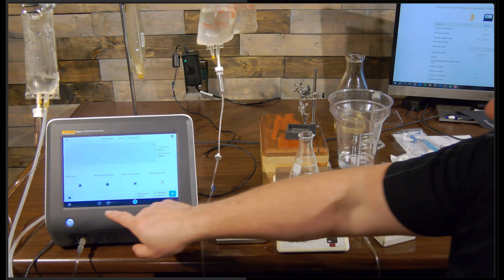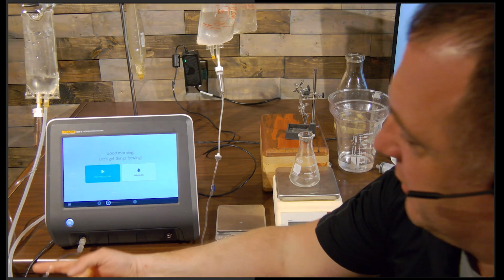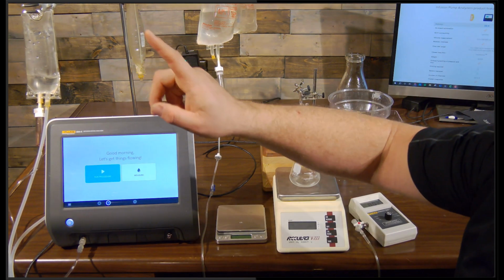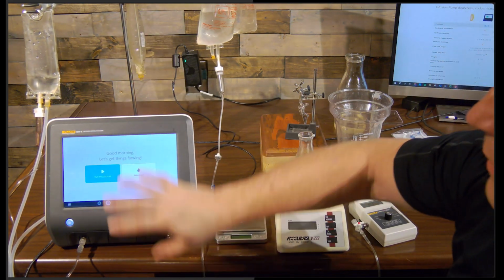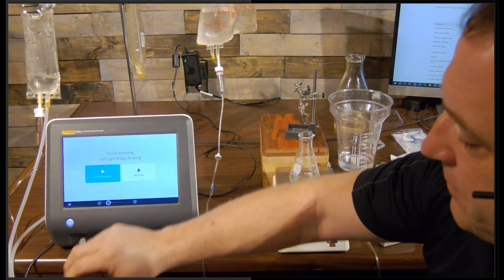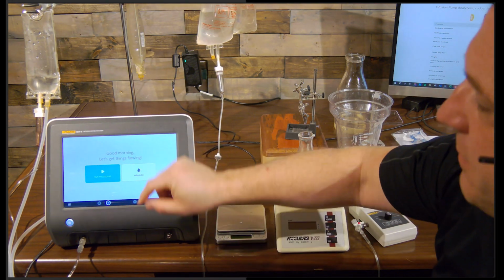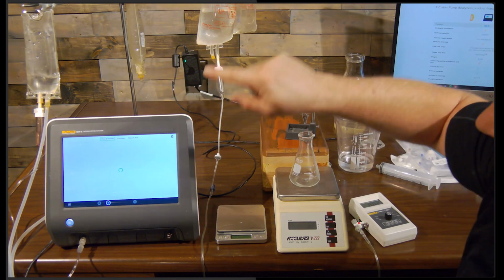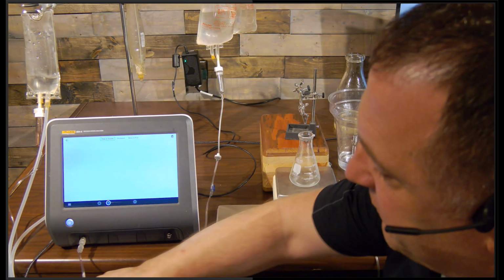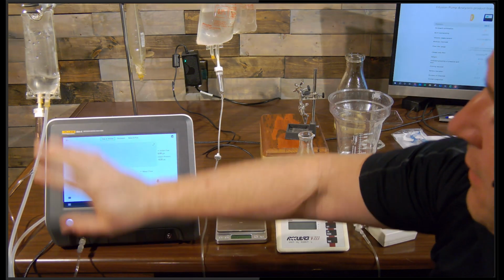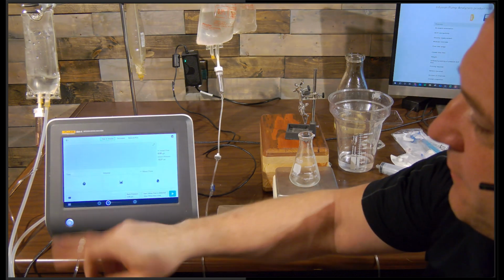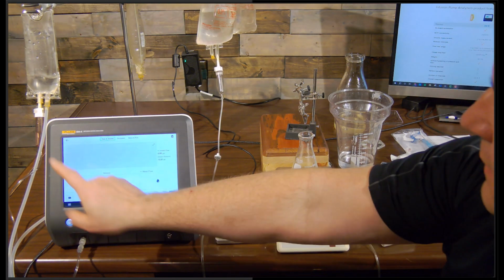How would I test? I'd go to channel 1. I'm hooked up to channel 1 right now. And I could either use the onboard automation, but if I'm using some of the infusion pumps that have to use their own calibration software, go to manual mode. And let's start with if I'm just using one set of tubing. If I'm that hospital that just uses one set of tubing, here I go.